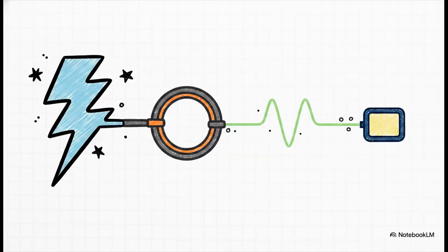Let's bring that physics back down to earth for a second and see how it translates to the actual switchboard relays. The system takes that terrifying 3,200 amp fault current and perfectly steps it down into a tiny, completely harmless millivolt signal. Depending on your ship's specific supply frequency, it outputs just 150 millivolts at 50 Hz or 180 millivolts at 60 Hz. The winding can even stay open when the switchboard is in service. It seamlessly feeds these perfectly linear low-voltage signals straight to your protection systems, keeping the delicate relays far, far away from the lethal primary voltage.